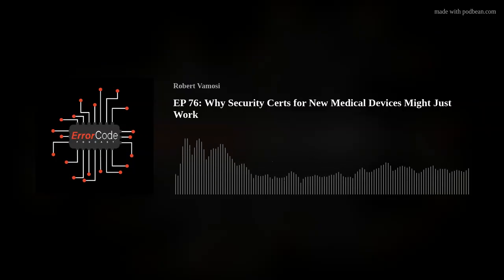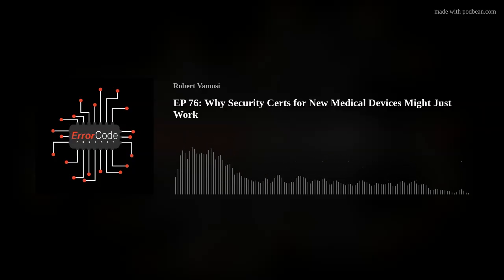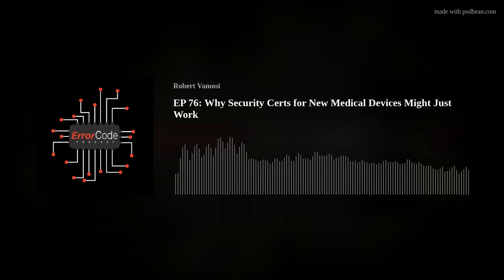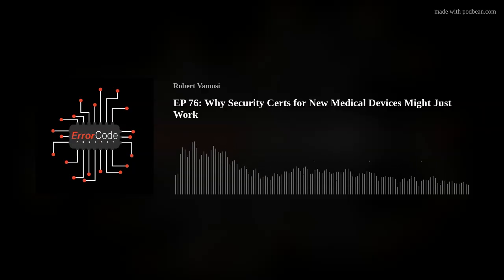Sometimes I have seen examples where a company will submit a device and say, here's what we did for cryptography, or here's what we did for this or that. And the FDA may go back and ask questions, saying we need an independent third party, not you, the large medical device maker, to say this thing is cryptographically secure, as an example. And so then that large medical device maker will have to hire an outside firm to do it, because it would be like you and I taking a test and self-grading ourselves. So, anyways, FDA will require those results. Sometimes they'll trust, hey, here's our product, here's our SBOM, here's our pen test results. Sometimes the FDA will dig into that a little deeper and say, we need another independent third party's results here to validate what you say.